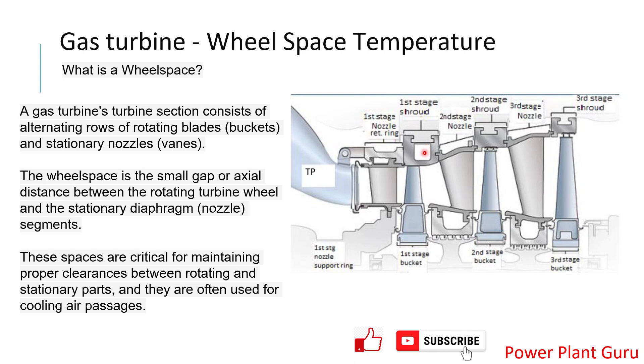Wheel space temperature measurement serves several purposes. As you increase the load, the wheel space temperature should also increase, and you can compare values over time. After a major or minor inspection, you can monitor the wheel space temperature at full load, then before the next combustion inspection or GPI, you can check how the temperature is changing at that particular load. This gives an indication of how turbine health is changing over time.